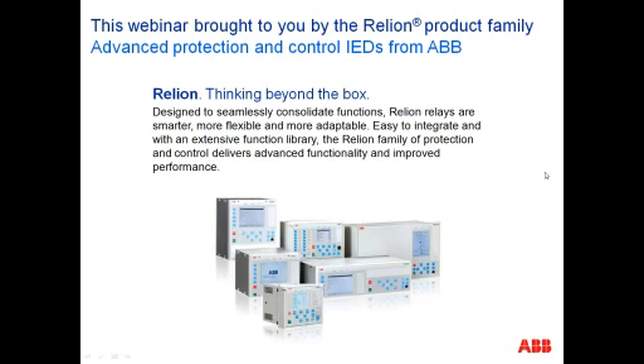Voltage is typically the 3V0 or 3V2, the zero sequence voltage or the negative sequence voltage, measured at the relay location. Regardless of whether the fault is on one side of the bus where the relay is applied or the other, the voltage quantity will not change, and you have to be familiar with symmetrical components to look at how that works.